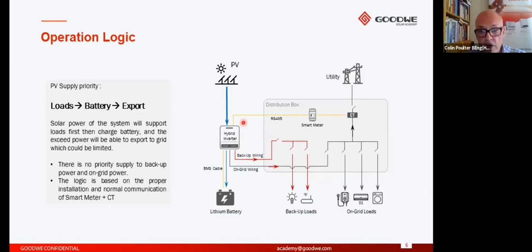Now, if we start to export that excess power very, very quickly, this CT is going to recognize the fact that there's power going out to the grid, and it's going to signal back to this smart meter, which is going to direct the hybrid inverter to not allow that power to go out to the grid. It's going to start charging the battery. Now, that battery will continuously charge as long as there's excess power. But once the battery has reached 100% state of charge, then the only thing that can happen is that the power is going to start to be exported out onto the grid. And that's the essential charging logic that we have here.